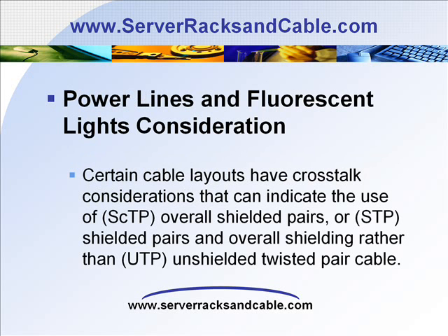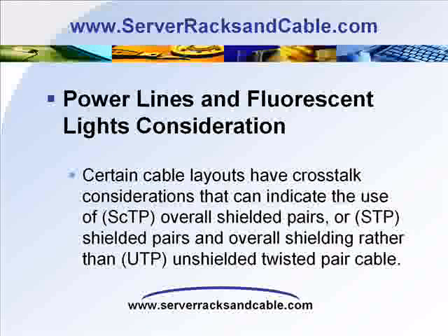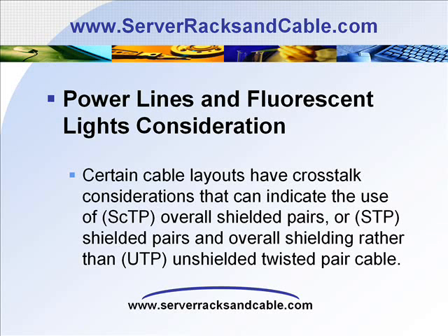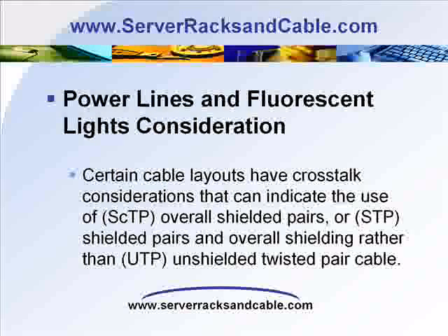There are also considerations when the cable runs near power lines or fluorescent lights, where there is a possibility of increased crosstalk that may have to be dealt with. In a well-designed data center cable layout, there are often four separate layers of cables including copper cables, fiber cables, power cables, and ground lines. Certain cable layouts have crosstalk considerations that can indicate the use of SCTP overall shielded pairs or STP shielded pairs in overall shielding, rather than UTP unshielded twisted pair cable.